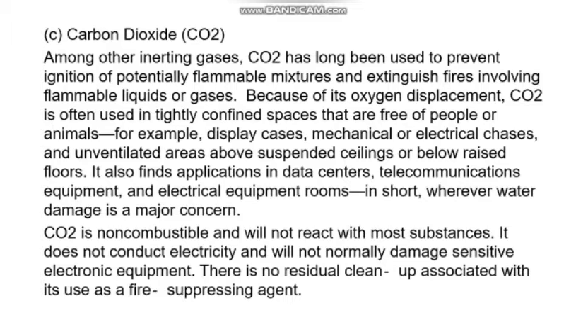Another example is carbon dioxide. Among other inerting gases, CO2 has long been used to prevent ignition of potentially flammable mixtures and extinguish fires involving flammable liquids or gases. Because of its oxygen displacement, CO2 is often used in tightly confined spaces that are free of people or animals. For example, display cases, mechanical or electrical chases, and unventilated areas above suspended ceilings or below raised floors. It also finds application in data centers, telecommunications equipment, and electrical equipment rooms. In short, wherever water damage is a major concern.